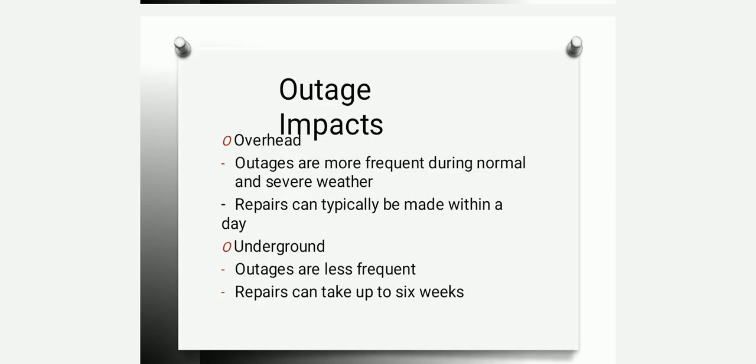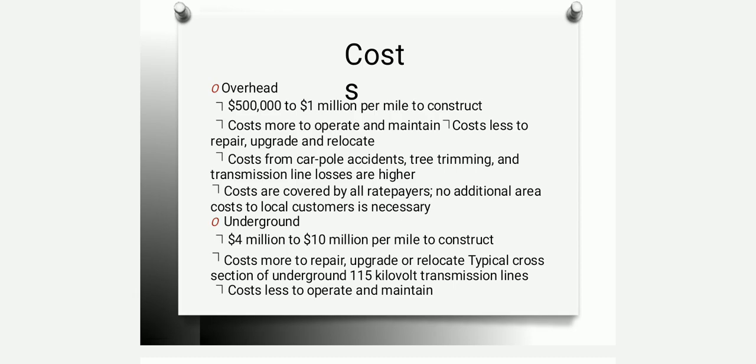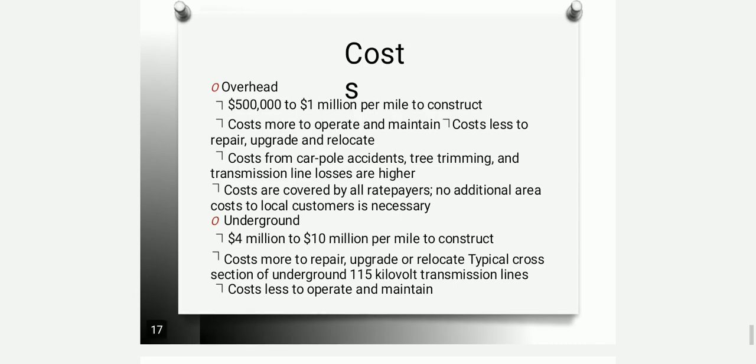For outage impacts, overhead outages are more frequent during normal and severe weather conditions but repairs can typically be made within a day. For underground, outages are less frequent but repairs can take up to six weeks minimum. The cost to construct an overhead line is $500,000 to $1 million per mile. This gives the representation of cost for laying down both an overhead transmission line and an underground transmission line.